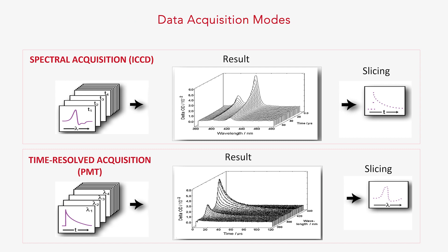The ICCD detector in the LP980 allows acquiring the full transient absorption spectrum in one laser shot. The spectrum corresponds to a single delay after the pump pulse. Conversely, the PMT detector provides a full kinetic decay in one laser shot, acquired at one wavelength only. Both detectors can provide spectral or kinetic information by acquiring time or wavelength maps and then slicing the data.